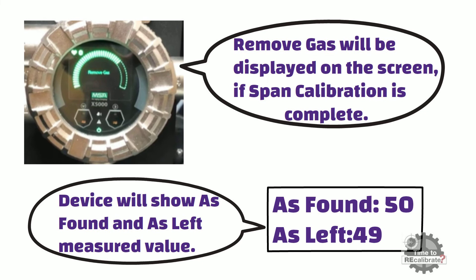It means that device span is set for 50% lower explosion limit, and the as left value is 49% lower explosion limit. It means that the measured value is 49% lower explosion limit.